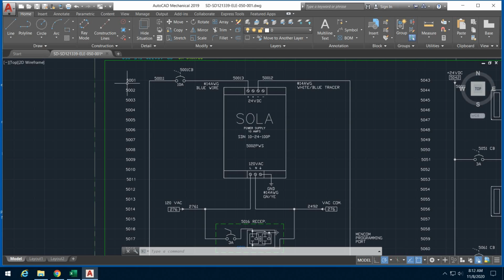So what you have is line 50. I'm sorry, you have line 01 of sheet 50. So you can see that, right? So that's what this is. 50 line 10, 50 line 11, 50 line 12. And what happens is this breaker is essentially page 50, line 1 circuit breaker.